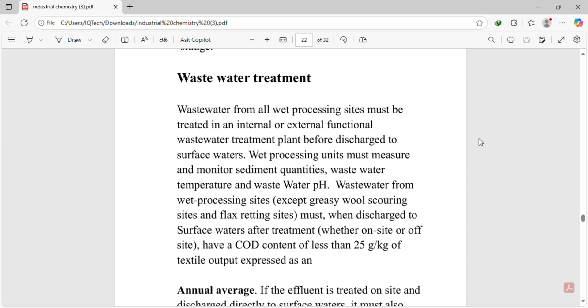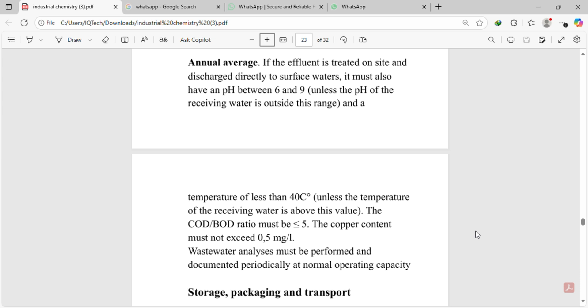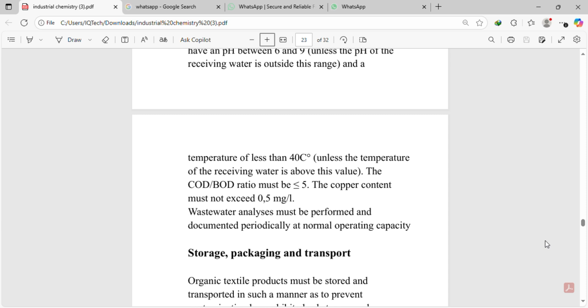If discharged directly to surface water, it must also have a pH between 6 and 9 unless the receiving water has a pH outside of this range, and temperature less than 40 degrees unless the temperature of the receiving water is above this value. The COD or BOD demand must be less than 5 and the copper content must not exceed 0.5 mg per liter. These are the four basic rules for discharging water: pH between 6 and 9, temperature less than 40, COD or BOD demand less than 5, and copper less than 0.5 milligram per liter. Wastewater analysis must be performed and documented periodically at normal operating conditions.